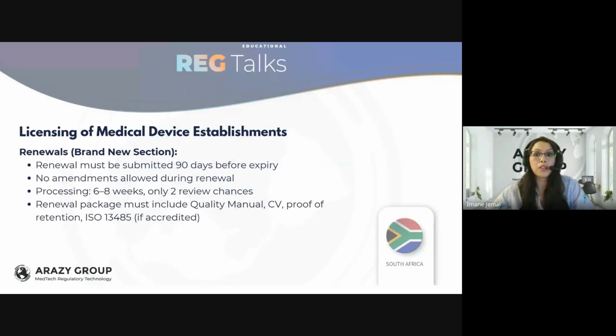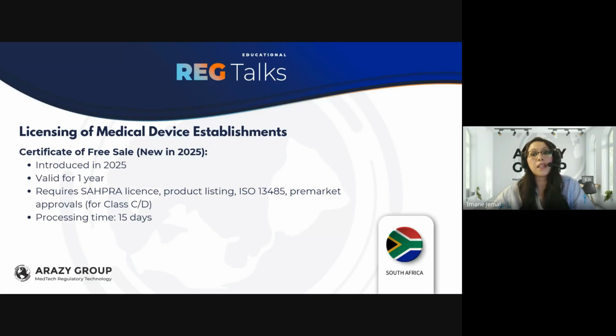That's regarding the renewal. Now, this is one of the biggest additions in this updated version regarding exporters, which can now apply for a CFS. It's valid for a year and confirms that devices are legally sold in South Africa, and requires both ISO 13485 certification and proof of pre-market approval for higher risk devices. Importantly, it's a quick process now, just 15 days if the submission is complete.